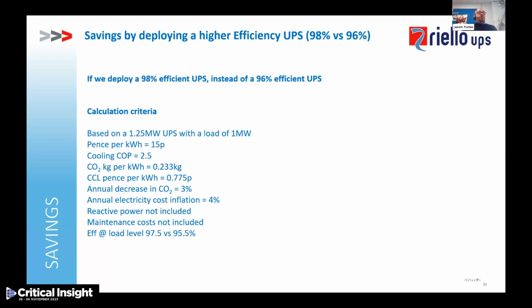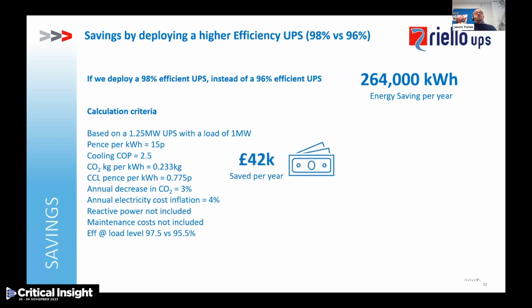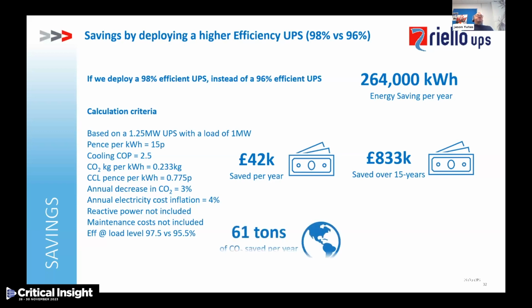At those load levels, traditionally, the high efficiency machine will be running at around 97.5% and the lower machine at 95.5%. That would equate to a typical annual saving of around 264,000 kilowatt hours per year. That comes out at £42,000 saved a year, which over 15 years would come to £833,000, resulting in 61 tons of CO2 saved over a year, and over 15 years, 715 tons. Obviously, these numbers would massively change depending on the installation type, and if it's legacy equipment, they can be nearly double or even triple.